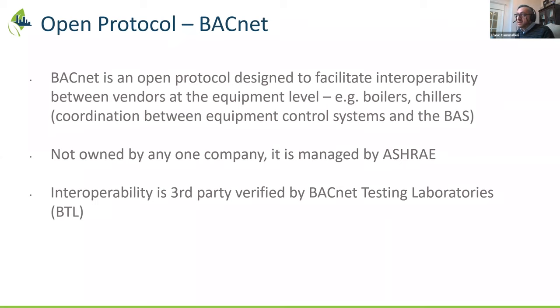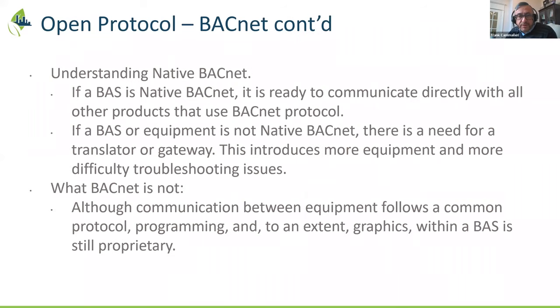Okay, next, a little bit of background to understand some of the detail with BACnet. There's this understanding of native BACnet. Basically, a BAS that's native BACnet comes out of the box ready to communicate with all other products that use the BACnet protocol, things like VFDs, boilers, and chillers that may have BACnet cards. A BAS that is native BACnet can communicate directly with it without needing any other devices. If a BAS or equipment is not native BACnet, there's a need for a translator or gateway.